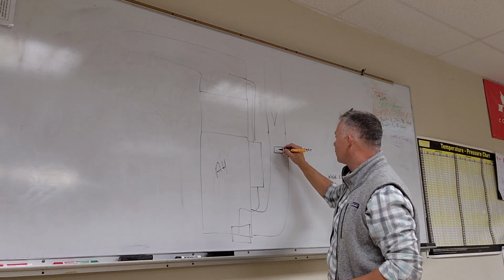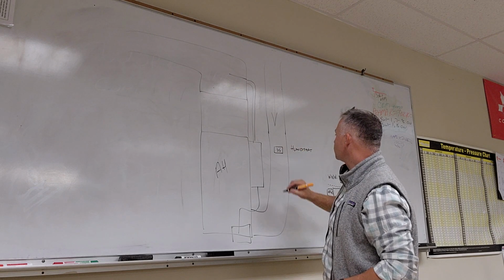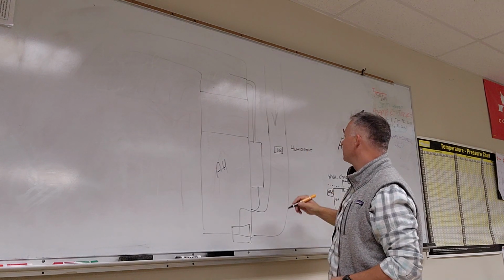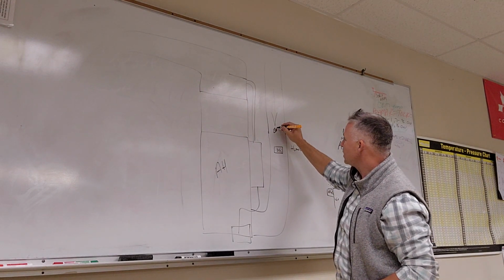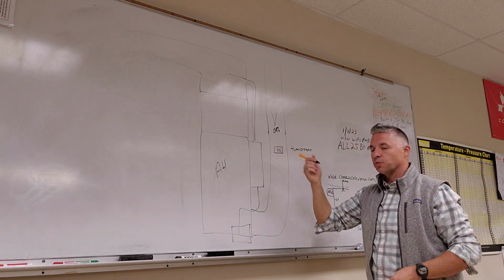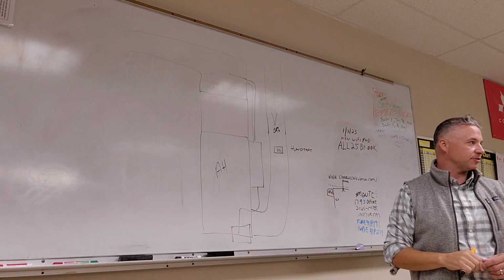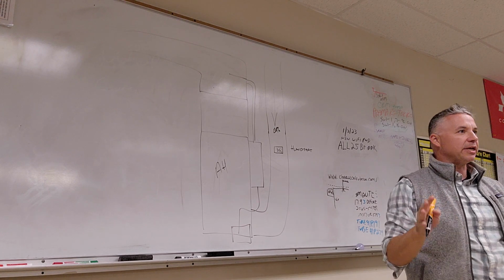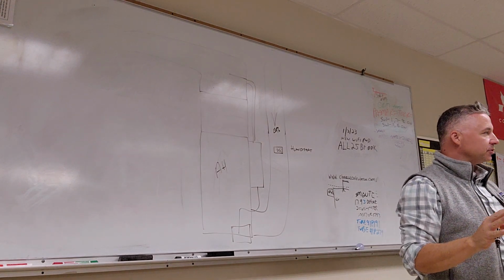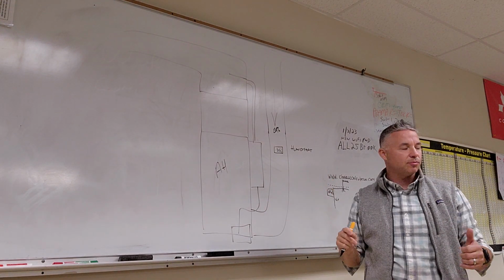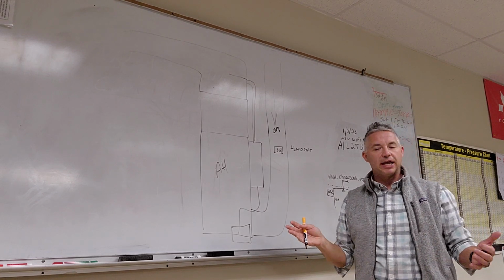We're setting this for, let's call it 35% as our setting. So if the air coming back is at 20%, this switch is going to say, I need humidification. Okay? But that's not enough. We need more information to know if it's okay to operate the steam humidifier. We want to collect more data.